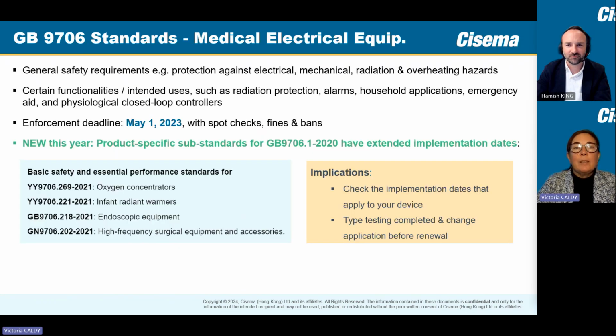Now we come to the GB standards, which cover medical electrical equipment. This has had a lot of coverage over the last few years, as it is a standard change that has affected and continues to affect a lot of devices. So here it's just a short reminder and a quick update on the situation. It's a standard that covers general safety requirements for protection against electrical, mechanical, radiation and overheating hazards. So it can cover products with certain functionalities or intended uses, such as radiation protection, alarms, household applications, emergency aid, etc. So it covers quite a wide range of products.